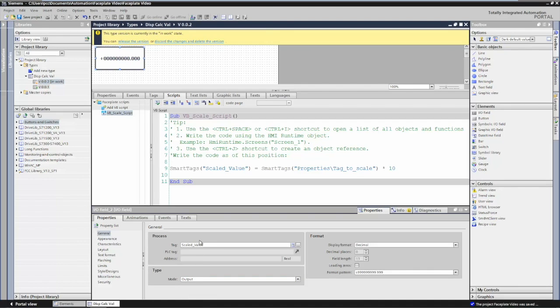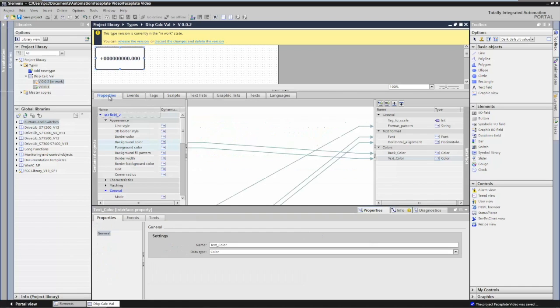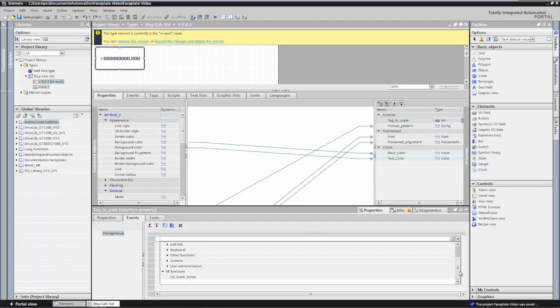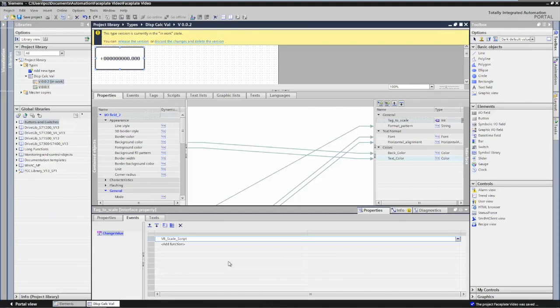The next step is to go back to the properties section and trigger our script to run. In the properties, when the tag value that gets passed in — tag_to_scale — changes, I want to execute the script. So I'll highlight it, select the events tab, and there's a Change Value property. I'll select the script we just created — user defined scripts are at the bottom of the list, here's vb_scale_script. So now this script will execute anytime that property changes: if the value changes in the PLC, it triggers a change value, and then that will cause the value to scale.